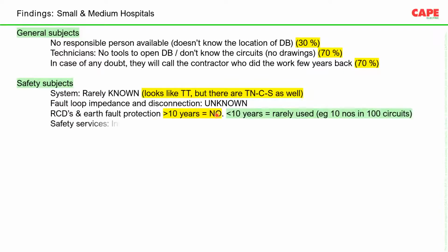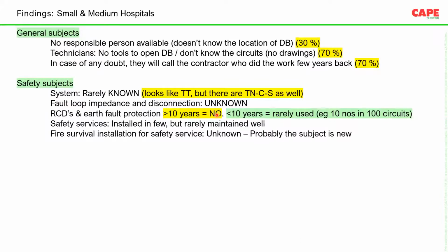With respect to safety, like system earthing: are you using a TT system or a TN-S system, or what kind of system earthing are you doing? Unfortunately, 100% of people don't know. The second question with respect to safety should be, have you tested the efficiency of automatic disconnection of supply? But instead I changed the question: have you tested the fault loop impedance and disconnection? The answers are not encouraging.